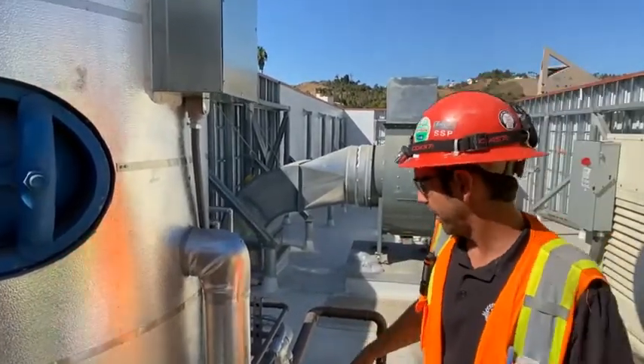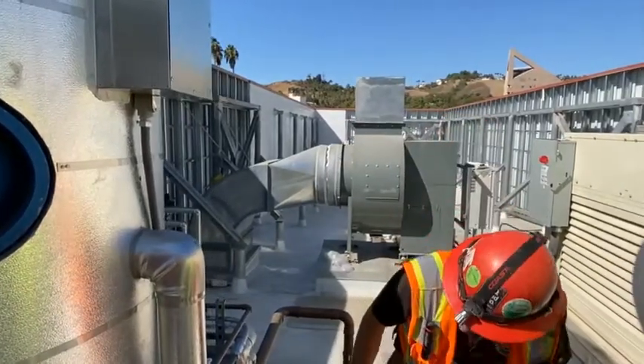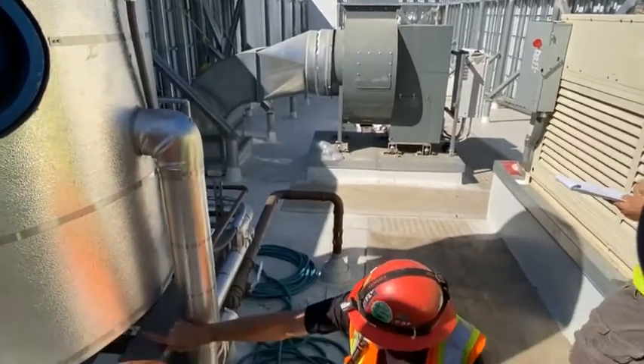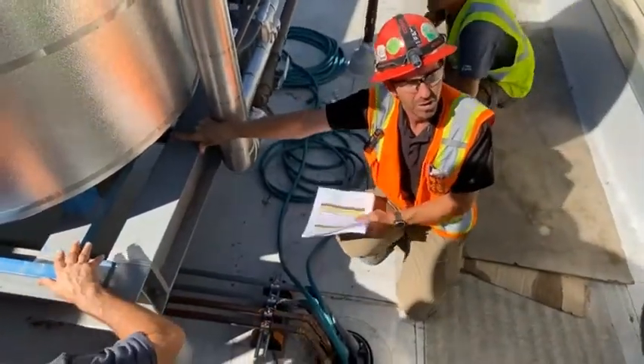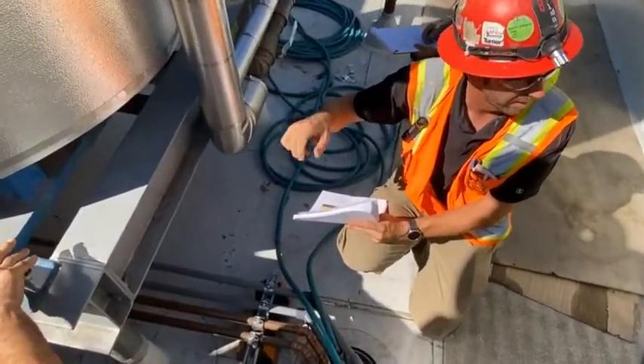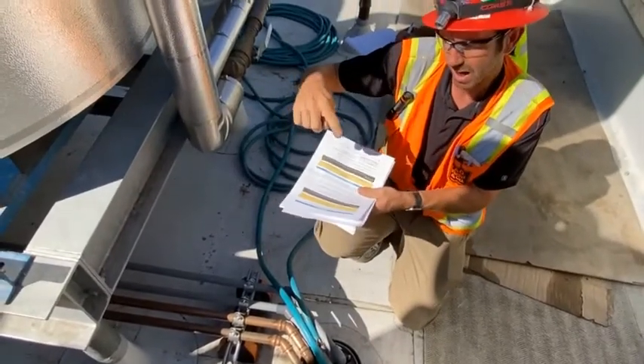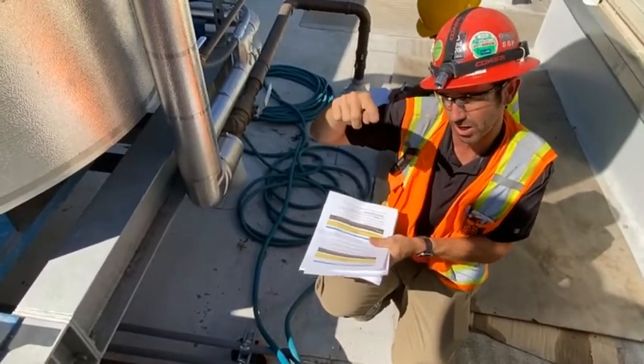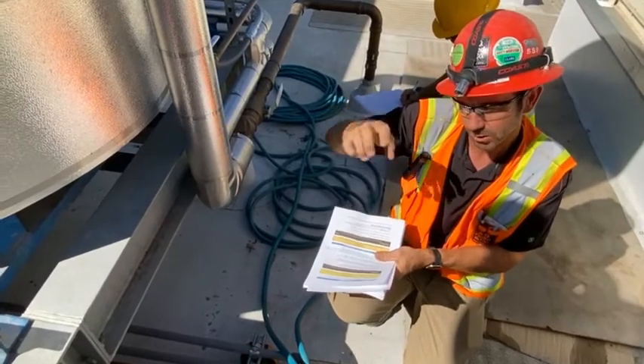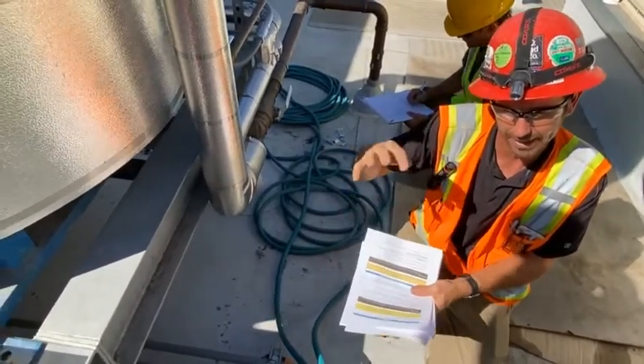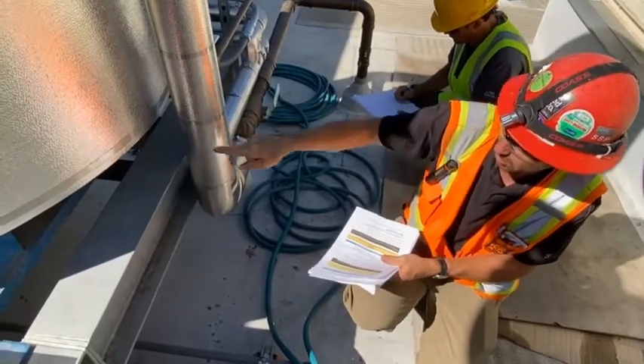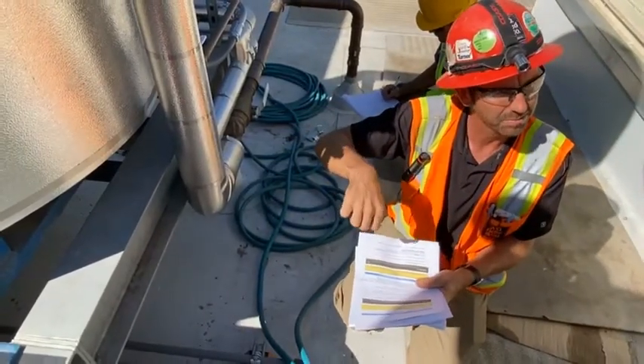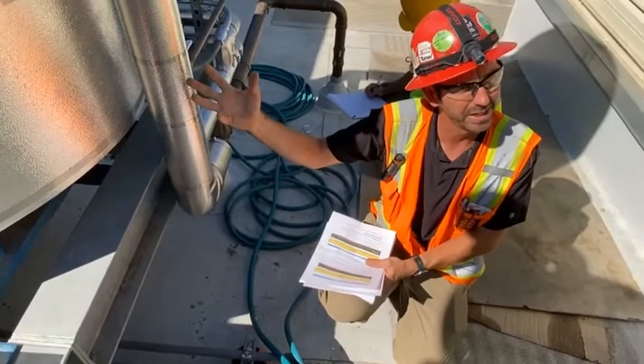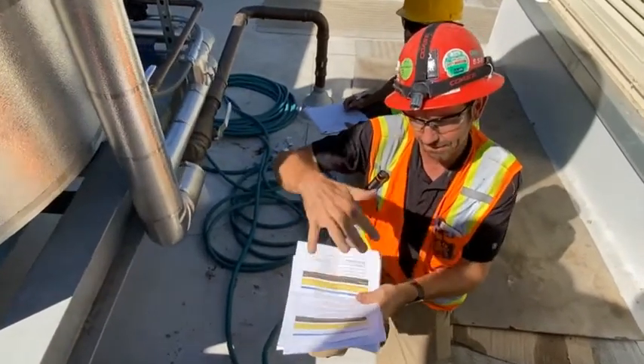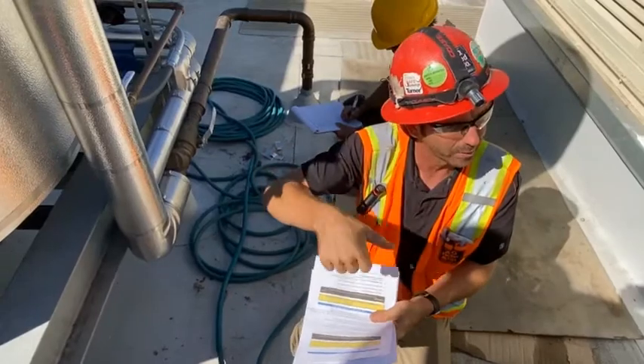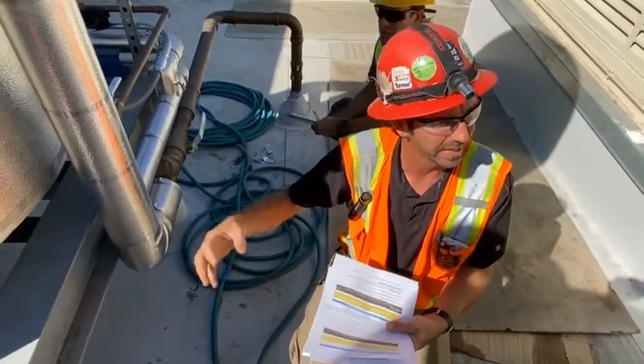So monthly, we also want to open the drain on the bottom of the tank. Down at the bottom of the tank here, we have a 1.5-inch valve. Right now, there's just a 1.5-inch plug at the bottom of it. What we'll want to do is, I'd recommend putting like a 1.5-inch straight nipple. So a 1.5-inch nipple by at least like 12 inches or so will fit in here, and then reduce down. So if there's any debris or any sediment in the tank itself, you'll have a full size height to blow it down into, and then reduce it in case there is debris.